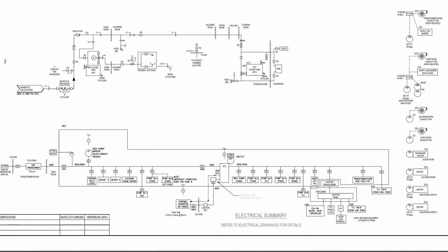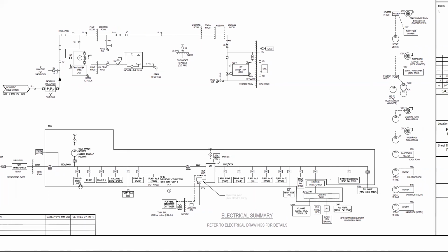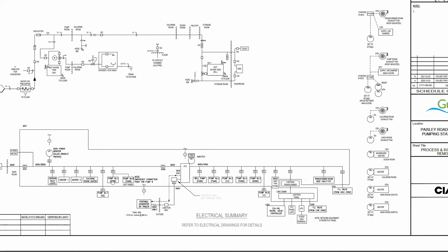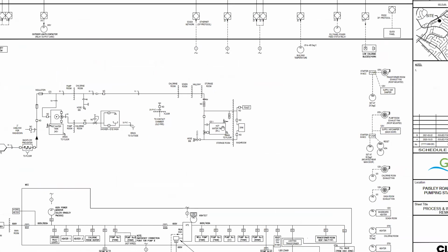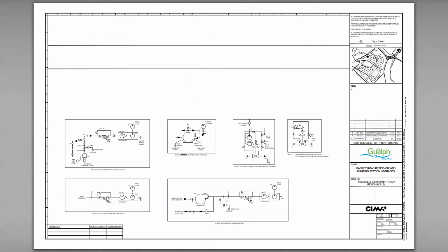Again, this one shows even less detail than the last drawing, which talked about pad mounted oil filled transformer, power monitors. We've got disconnects. It doesn't even list the sizing of these lines going out to those pumps because these ones are all being ripped out. We've got 600 volt here. We got 600, 400 amp after the ATS, a portable generator, well pumps, pump 1, pump 3, pump 4, pump 5. So this is an even less detailed one, but we know where the devices are and what the voltages are coming to them. And later on, if we need to, we can dig through and find more information.